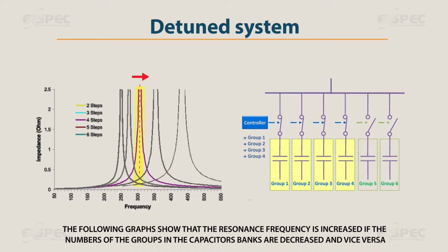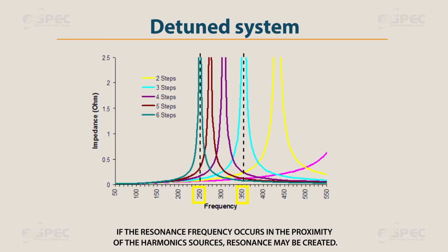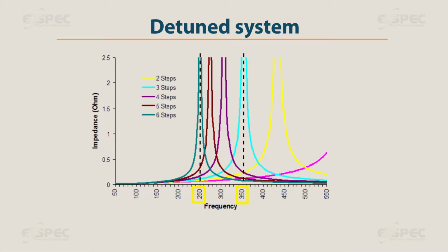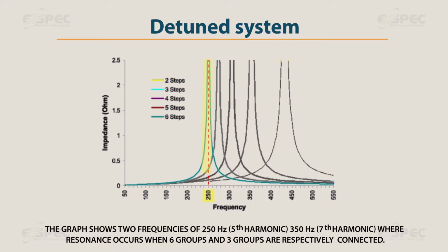The graph shows that the resonance frequency is increased if the number of groups in the capacitor banks is decreased and vice versa. If the resonance frequency occurs in proximity of the harmonic sources, resonance may be created. The graph shows two frequencies of 250 Hz, 5th harmonic, and 350 Hz, 7th harmonic, where resonance occurs when 6 groups and 3 groups are respectively connected.